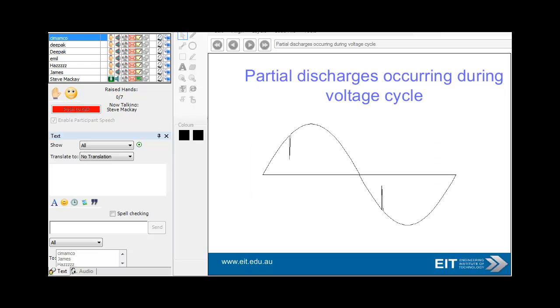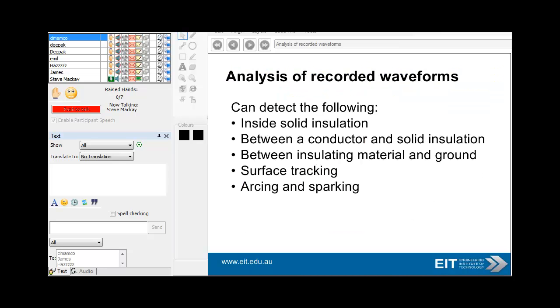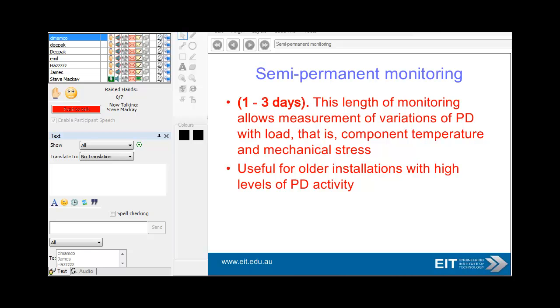Insulation testing: partial discharges occur during the voltage cycle. Analysis of recorded waveforms allows you to detect faults inside solid insulation between conductors, between insulating material and ground, surface tracking, arcing and sparking. Partial discharge monitoring gives more accurate measurement by capturing short-term variations of one to two hours, and semi-permanent monitoring up to three days gives measurement of variations of load, temperature component, and mechanical stress.